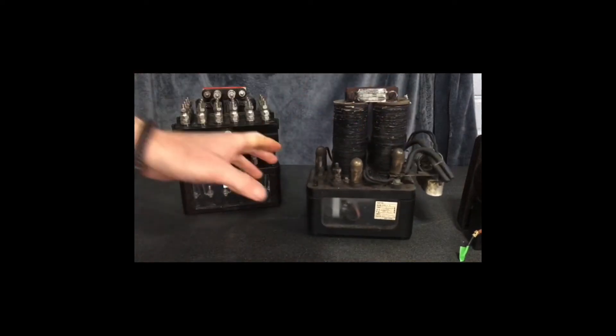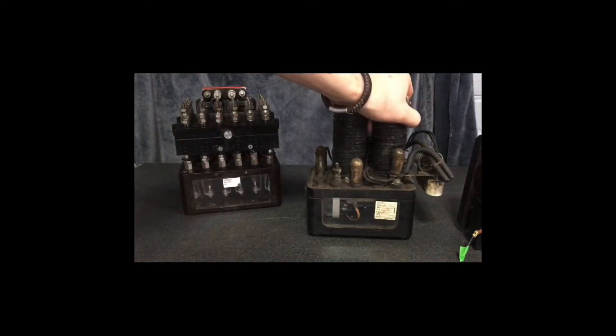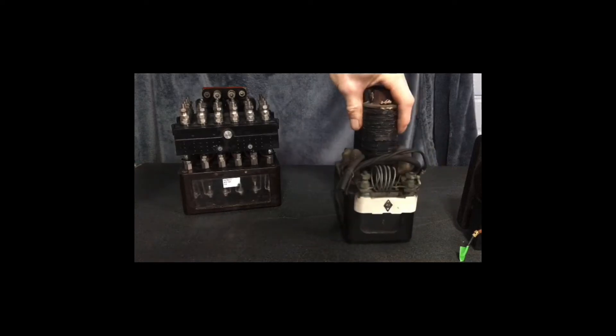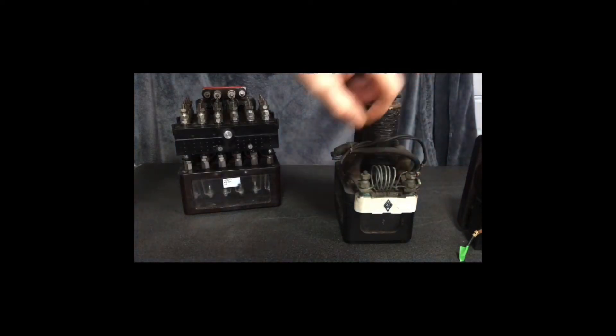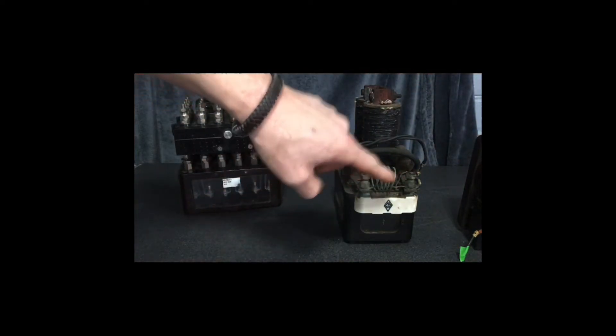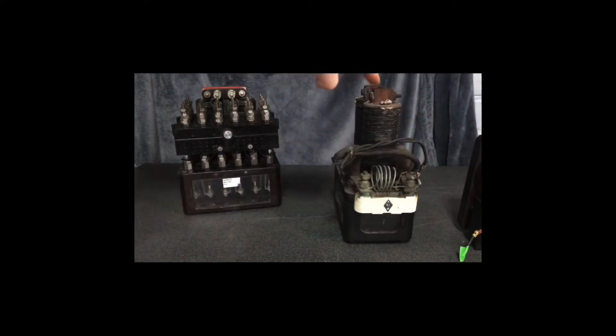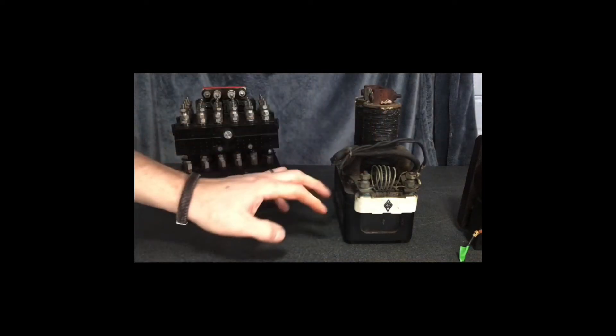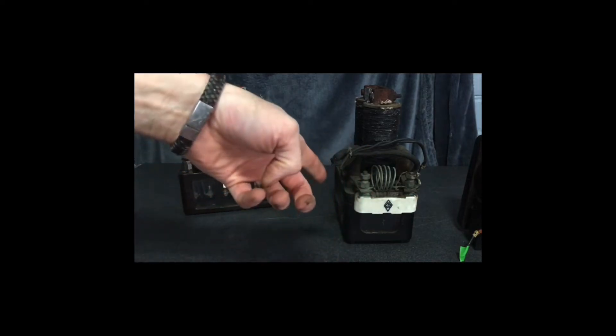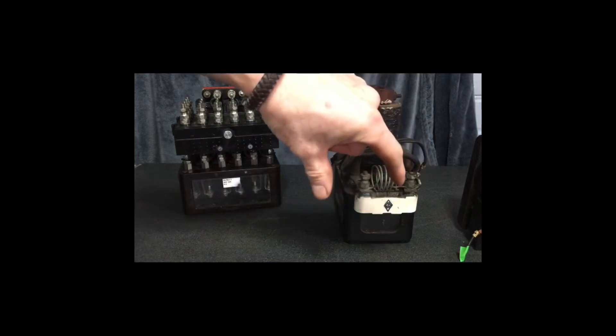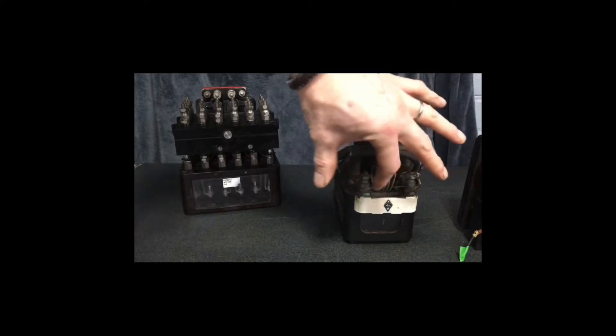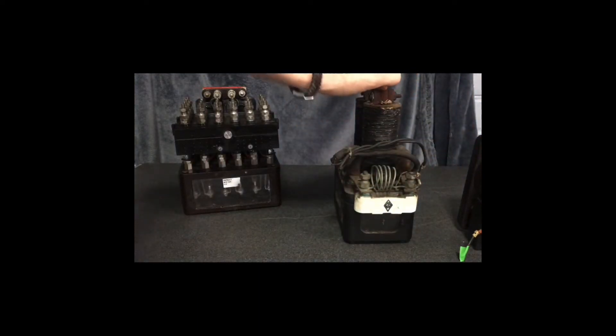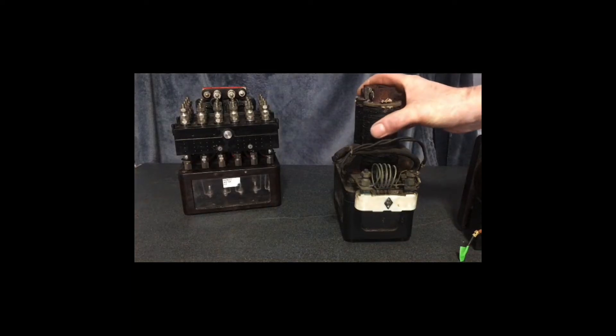This shelf-type relay, a much older one, is a current-sensing relay for a lamp-proving circuit. Hence why on this one, it's actually had a small wire-wound coil put on the back of it. This acts as a resistance. What will happen here, some of the voltage that drives the lamp is borrowed away to drive the relay. This will be a DC circuit because there's no rectifiers on it. There are plug-in versions of this that have AC rectifiers in. So you can take a little bit of the voltage for the lamp, turn it into a DC voltage. You can use this shunt or resistor to take the necessary amount of current to just keep the relay working. That way you can set it so when the lamp fails, it will drop out and warn the signal that the lamp has failed.